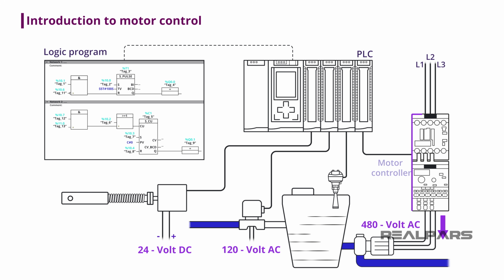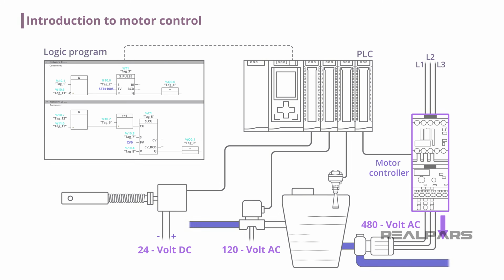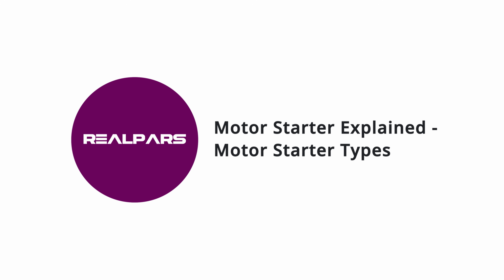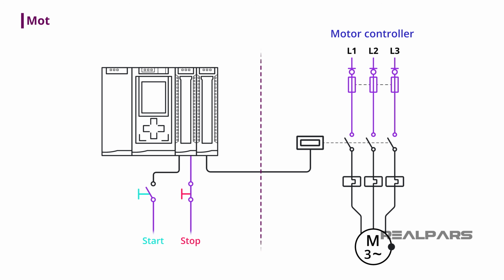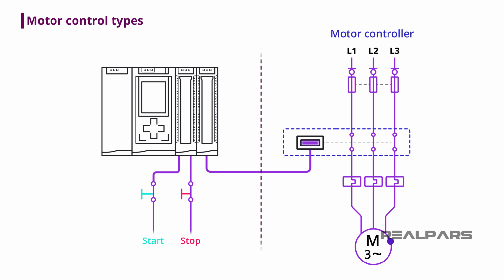The simple answer is by using a motor controller. Many types of motor controllers are available, and the various types and styles all have specific uses in industrial control. All motor controllers are designed to keep the motor from being energized until the controller is told to activate. Once activated, current can pass to the motor, which energizes the motor windings and starts motor rotation. Activation of the motor controller is typically accomplished with an electromechanical device built into the controller, also known as a contactor. Other methods can also be used.